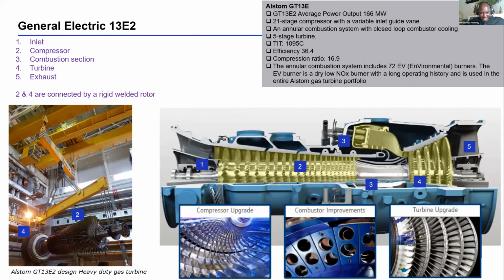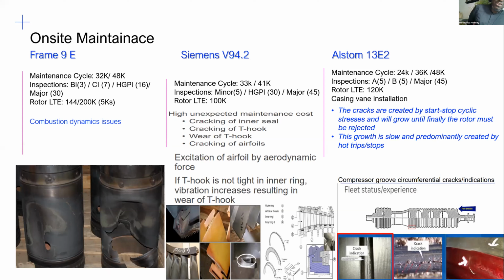So the same with the Alstom, but the good thing with the maintenance of the Siemens is that you don't open the machine onto your hot gas part. And this is almost at 24,000 hours. The same with the Alstom, you don't open it at all normally till the major inspection. But the GE, if it's a 32K machine, you open it at 8,000 hours or 12,000 hours. So this is like 1.5 years or 2 years, you have to do this.